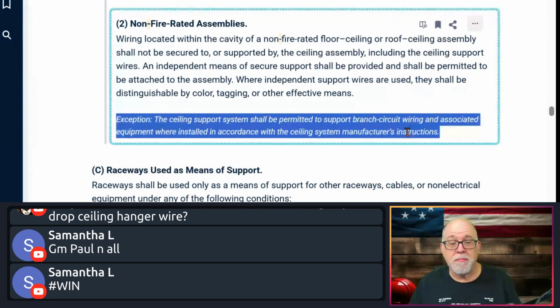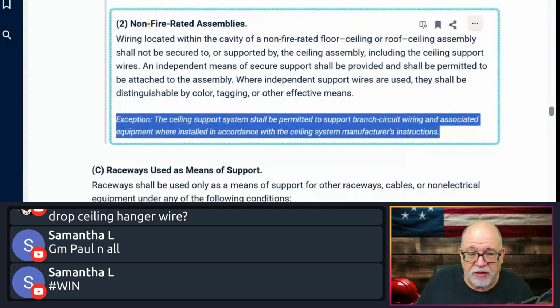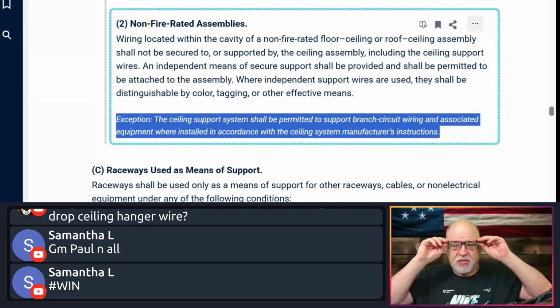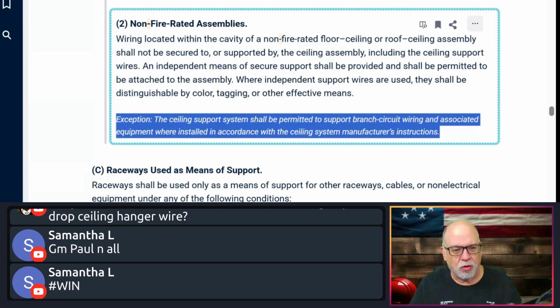So you may reach out to that grid manufacturer, not the installer. Don't make that mistake, because the installer is just an installer. He's getting paid 9 to 5 or 8 to 4, whatever it is. You need to reach out to the manufacturer of the grid and see whether or not it supports that. Why? Because to use this exception, there is a high probability that your AHJ, when they see all this, is going to want some type of documentation, because it says manufacturer's instructions. So that's where you're going to reach out. But in general, absolutely not.